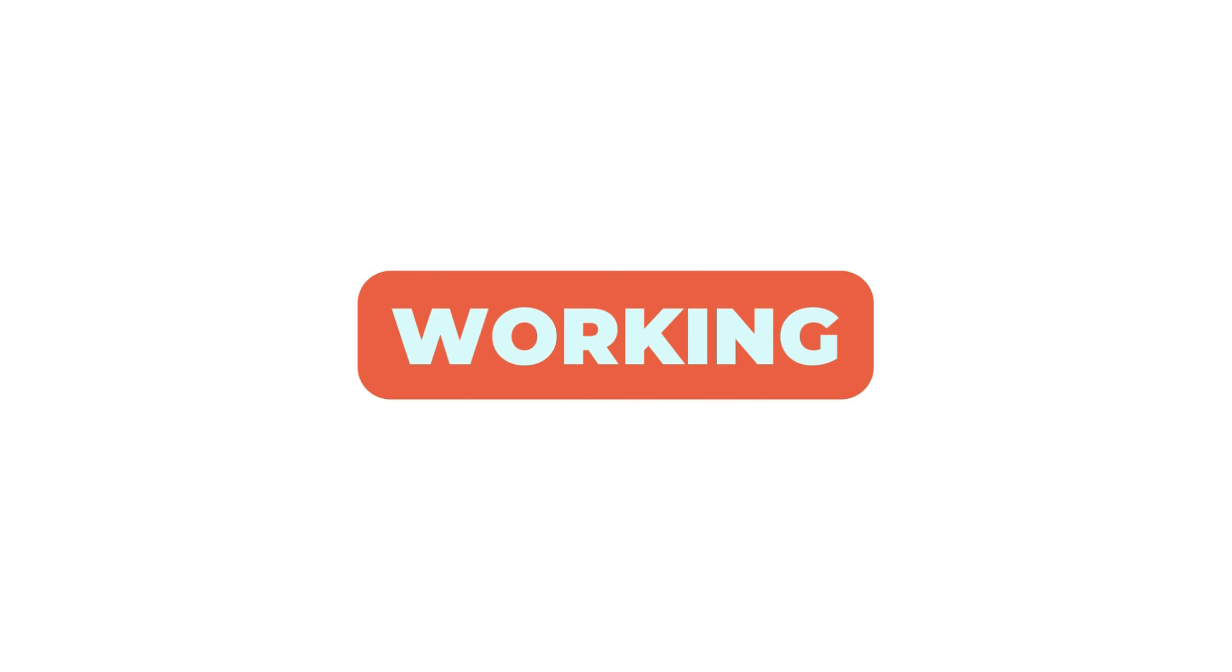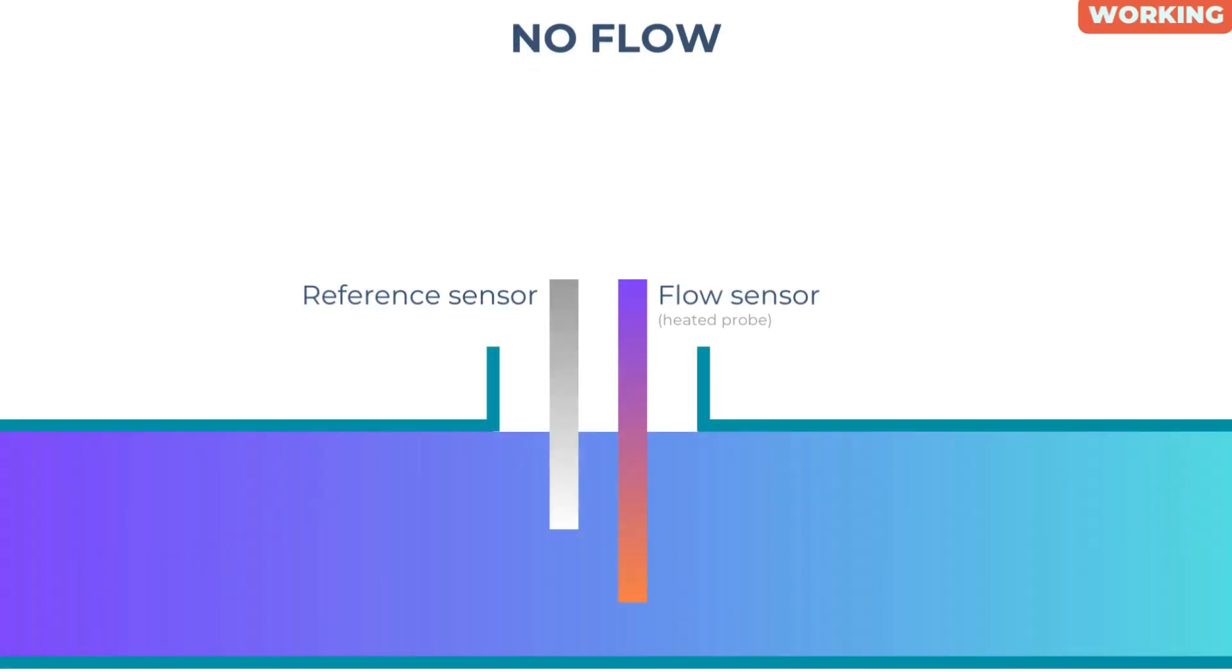Working of thermal mass flow meter: When there is no flow, the circuit maintains a continuous overheat, which is a constant temperature difference between the flow sensor and reference sensor.